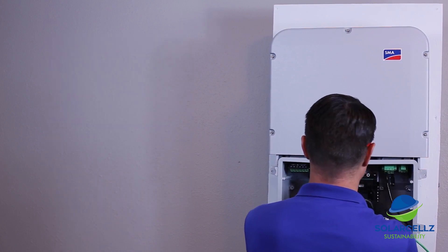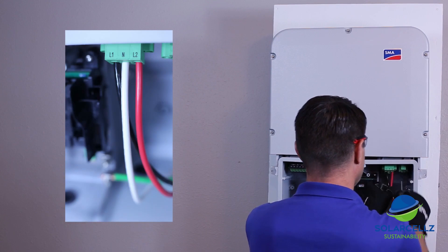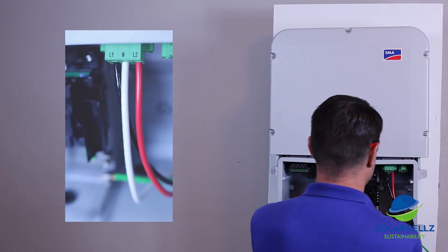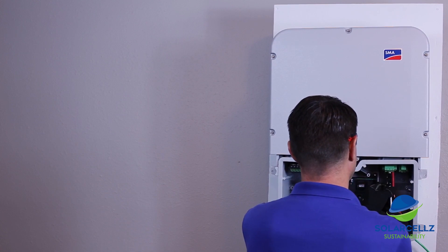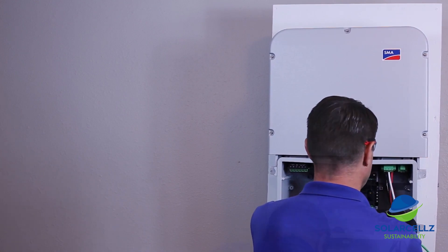Insert AC line 1 and line 2 conductors, and if appropriate, neutral. If installing line-to-line on a 208 volt or 240 volt Delta service, remember to select the correct grid code during commissioning.